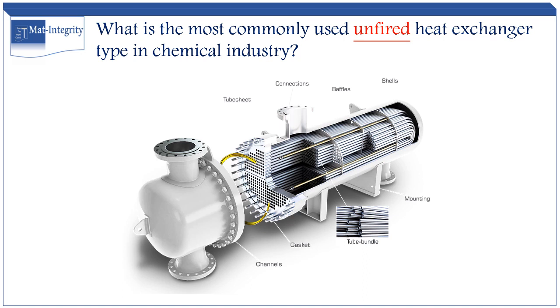Heat recovery is another key application. The name originally came from the main components of the equipment, which are the shell and the tube components. Typically, one fluid passes through the tubes, known as the tube side, whereas the other fluid passes through the shell, known as the shell side. Just imagine that you insert a small pipe inside a bigger pipe and then inject both pipes with different fluids to allow heat exchange between the hot and cold medium.